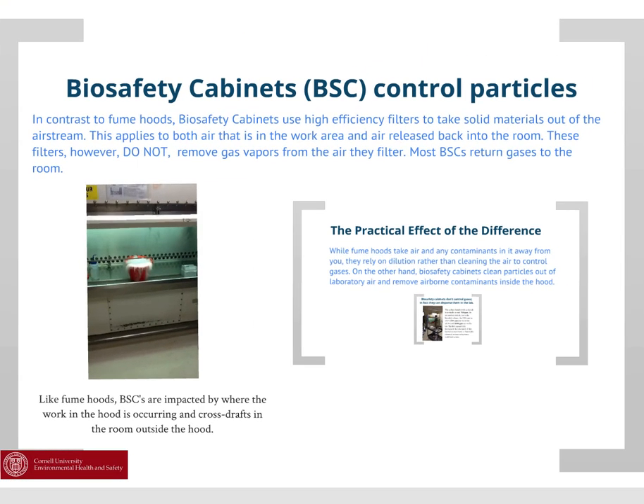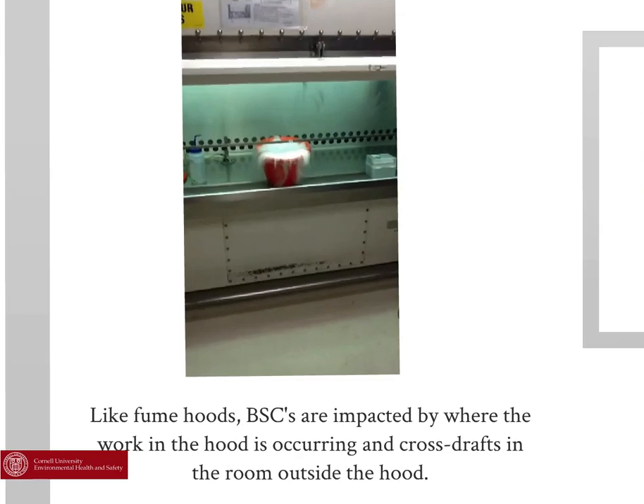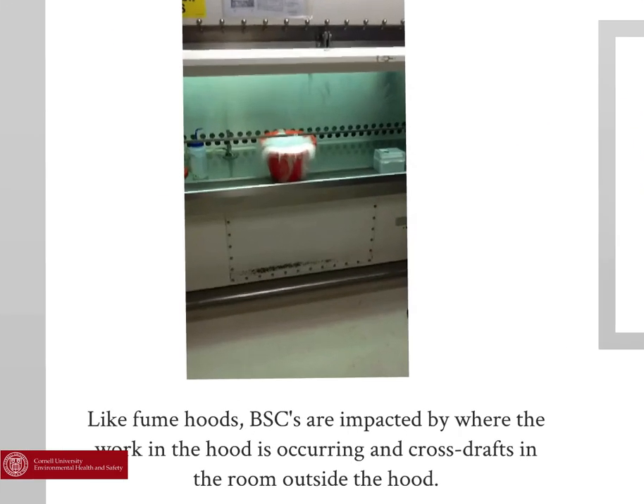Biosafety cabinets control particles. In contrast to fume hoods, biosafety cabinets use high-efficiency filters to take solid materials out of the air stream. This applies to both air that is in the work area and air released back into the room. These filters, however, do not remove gas vapors from the air they filter. Most biosafety cabinets return gases to the room. Like fume hoods, biosafety cabinets are impacted by where the work in the hood is occurring and cross-drafts in the room outside the hood.